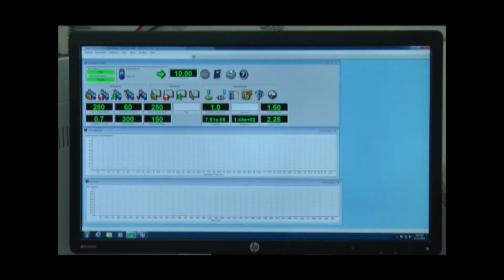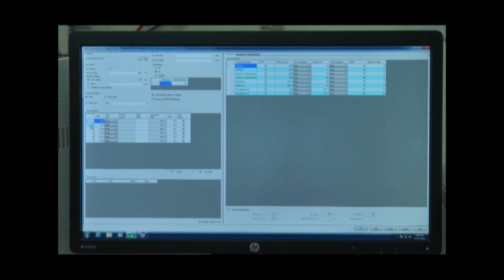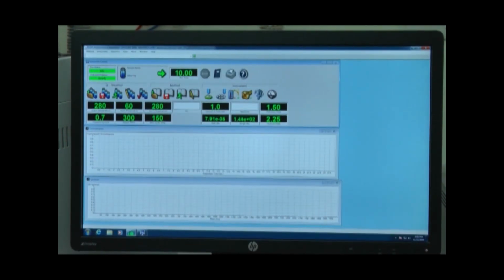This is the MS parameter. So these are time segments, and this is the multi-residue MRM method. So here we are doing more than 30 pesticides by this method, by GC-MS. These are the product ion, precursor ion, and these are the collision energy. Now the instrument is ready and in idle condition. So we are making a sequence.